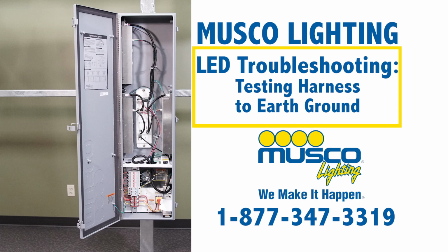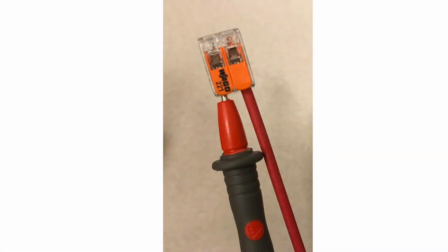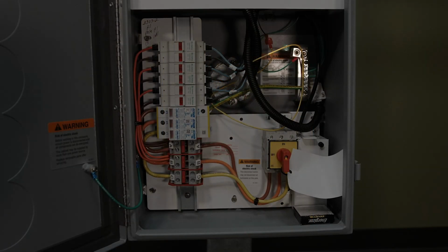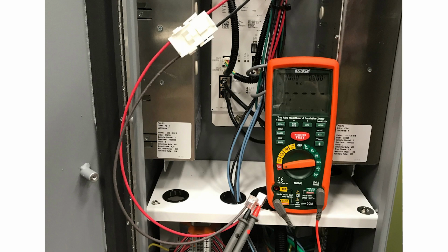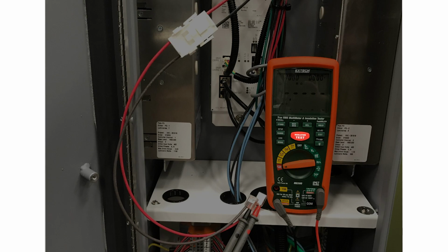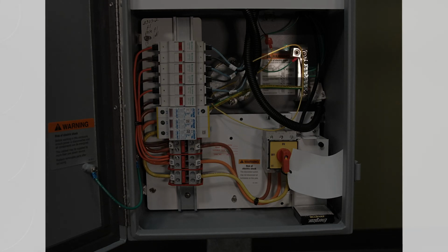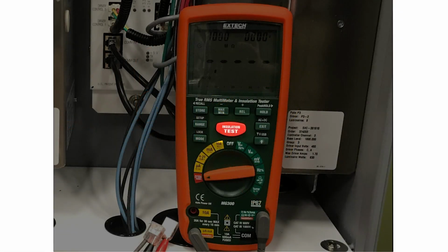After testing the fixture circuit, we will now test the harness for insulation leakage to ground. We will begin by hooking red probe to red harness wire and black probe to ground. There is a grounding lug in the bottom compartment of the enclosure that is ideal for this test. Press the insulation test button and hold for 45 seconds, recording both resistance and voltage if your meter gives you a voltage reading. You then move the red probe to black harness wire and keep the black probe on the grounding lug. Again, record the readings as above.